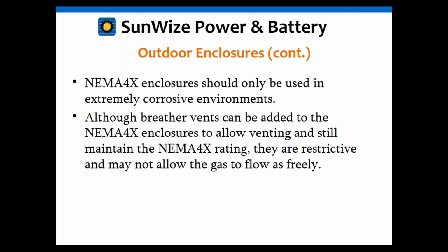The way to deal with that is to add breather vents to the enclosure. You can add vents that still maintain the NEMA 4X rating, but a lot of these vents are still somewhat restrictive—they don't allow gas to flow as freely as a 3R enclosure. It can be done, and you may need a whole bunch of these vents, but it becomes a bigger problem, so we generally recommend avoiding that if you can, since you still run the risk because the breather vents have restrictive flow.